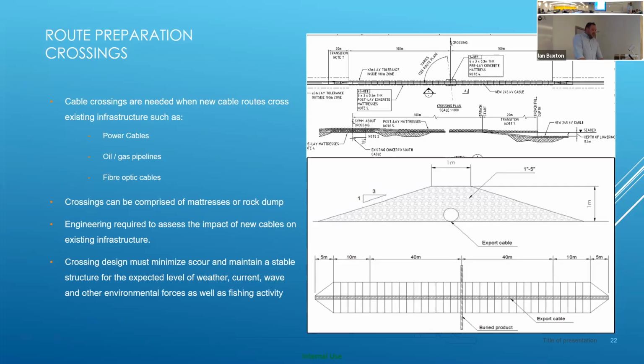We can build the crossings either out of concrete mattresses, which are 6 metres by about 3 metres and are put over the top of the cable as protective armour, or we can use what's called rock dump, basically a berm laid over the top of the cable post-installation. The purpose is to protect it mostly from fishing activity, but also errant anchor strikes, should a vessel be in trouble and drop its anchor, or drag over the top of it, to make sure you don't catch the cable and rip it out of the ground.